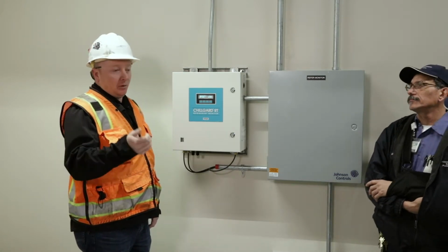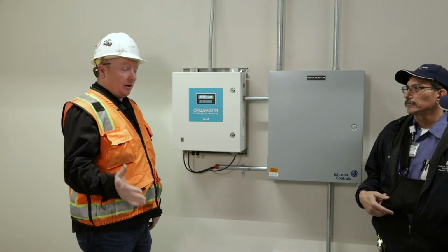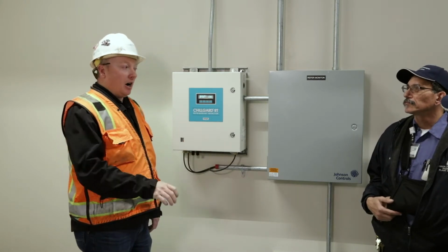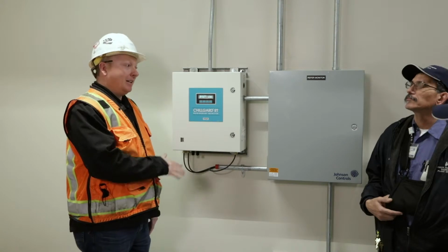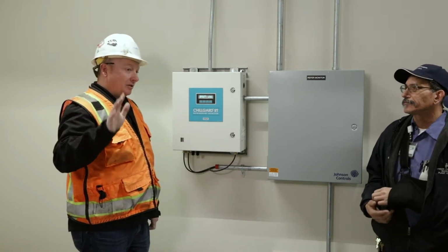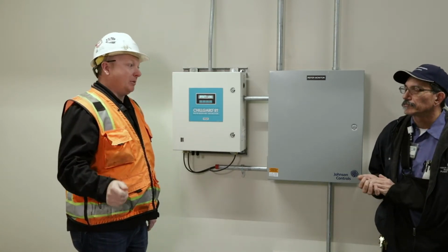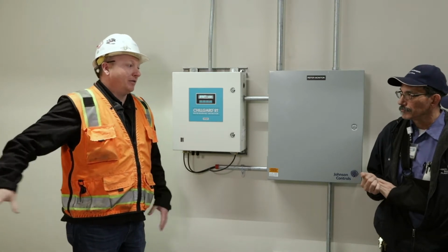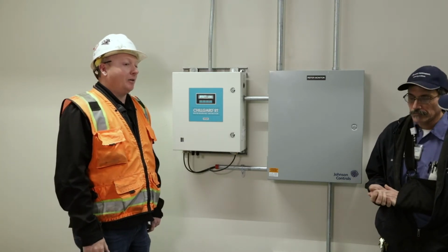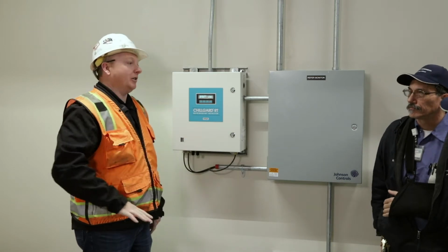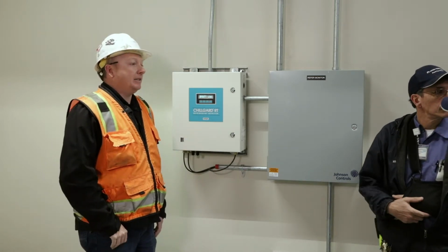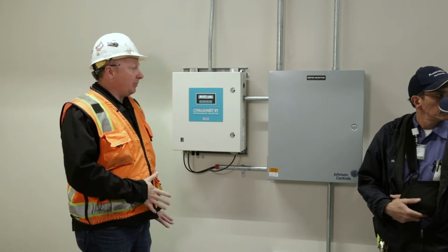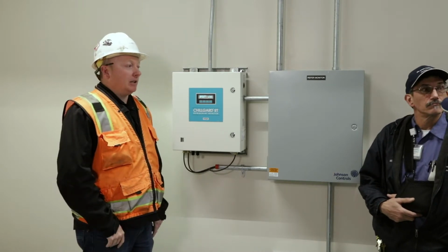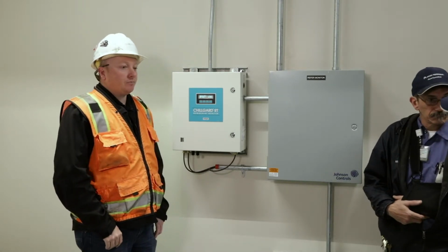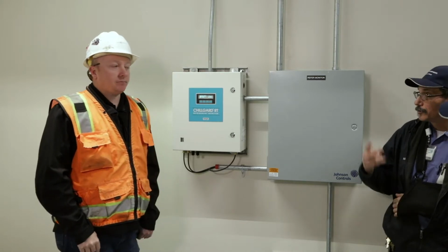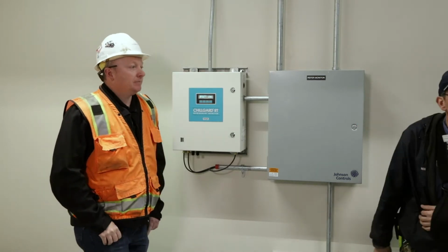That HOA, if you turn it to on, it'll just force it on through the BMS, and off will just keep it off through the BMS. There is an HOA at the actual starter of the fan that you can also manipulate. The one out here is really just for the system as a whole. If auto is going to let it work in leak detection or temperature control, anything like that. That's pretty much everything on this, unless you guys have any questions. Nope. All right. So there's only 2 sensors? 2, just one for each chiller.